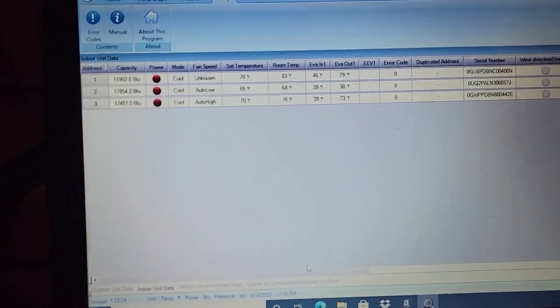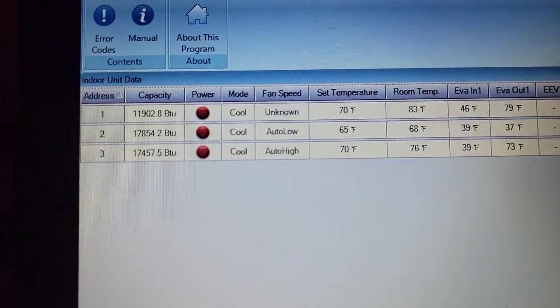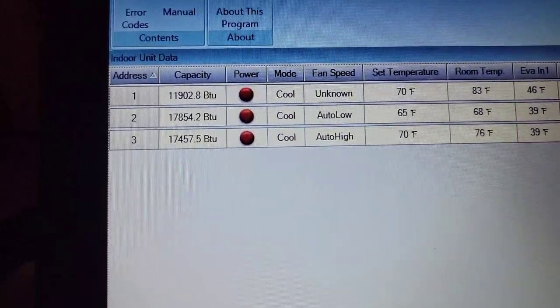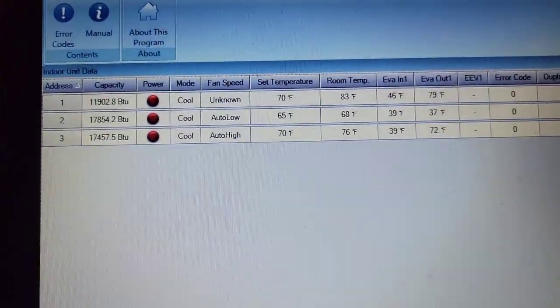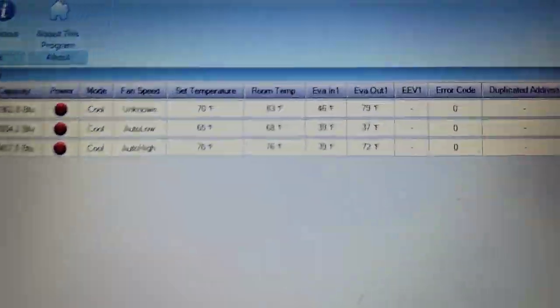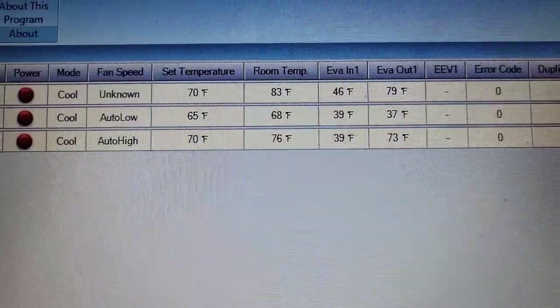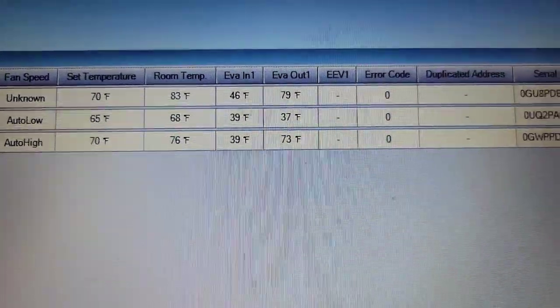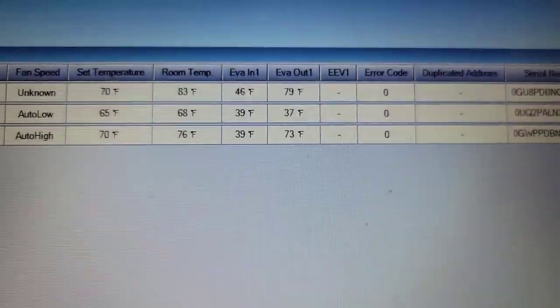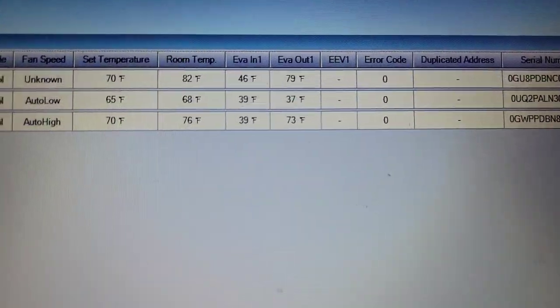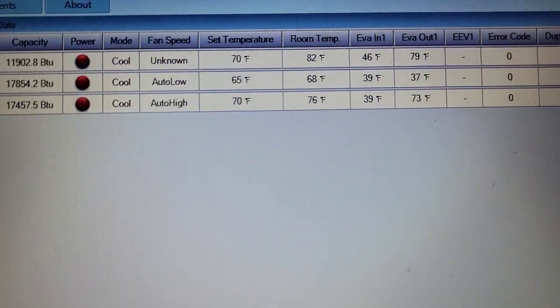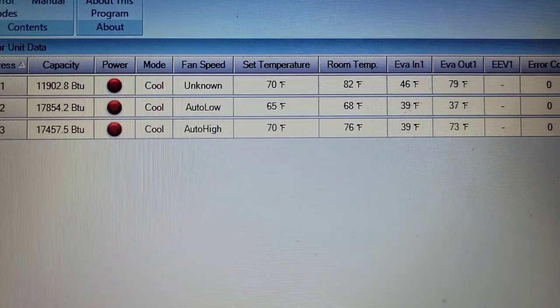Let's check out some of our data from the indoor unit. The mode is cooling. The capacity for each piece of equipment, I've got two 18,000 BTU units and a 12, and it looks like the capacity is pretty much maxed out there. Room temperature is 83, 68, and 76. Our evaporator inlet and outlet, that is measuring the sensor connected to each indoor unit.